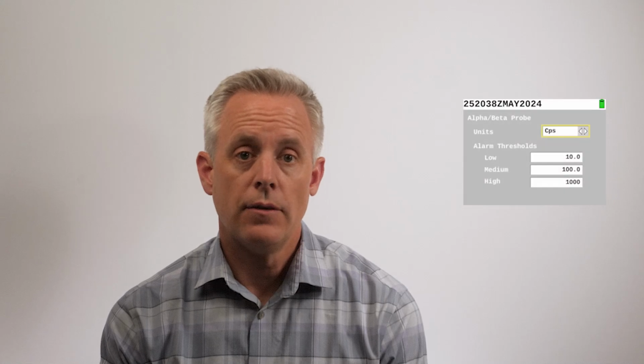On the probe settings screen, there is a channel field. If the probe has multiple channels, such as the alpha beta probe and the fiddler probe, you can change the settings for each channel. If the probe only has one channel, the channel option will not be available to change. Probe settings you can change include the units of measurement and alarm thresholds. The neutron probe has one additional setting for kilo-electron volt values.